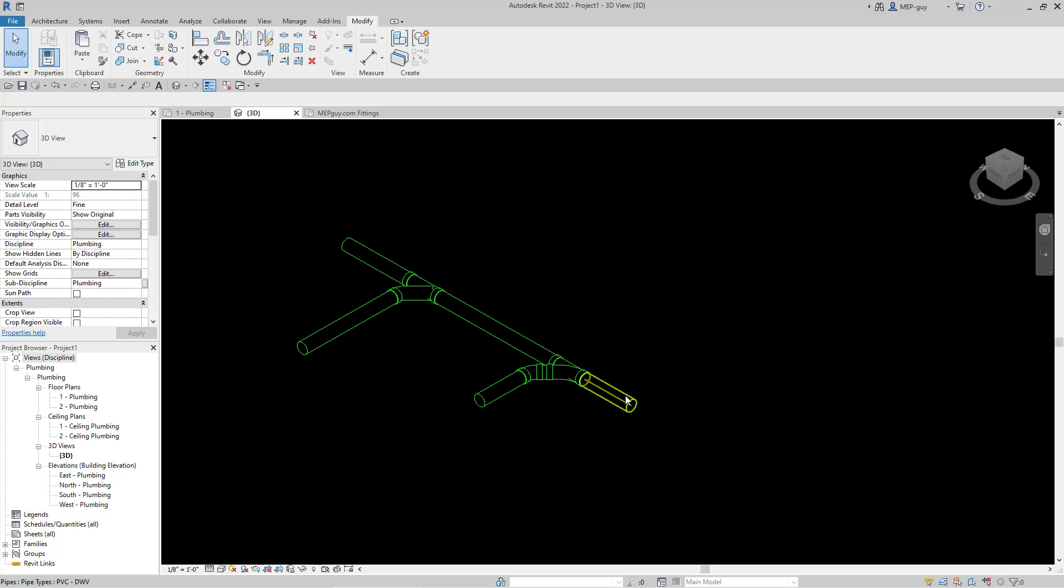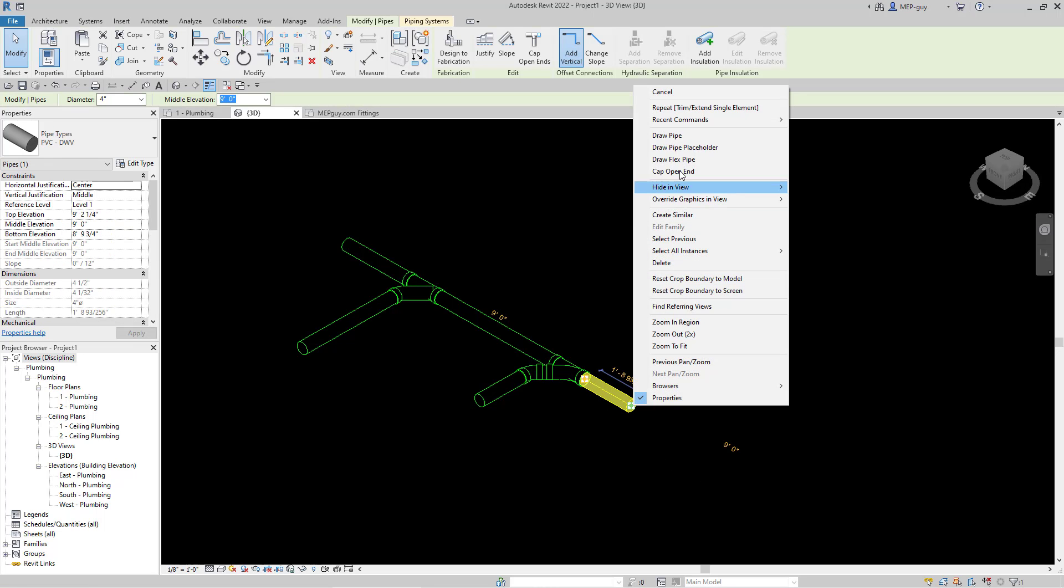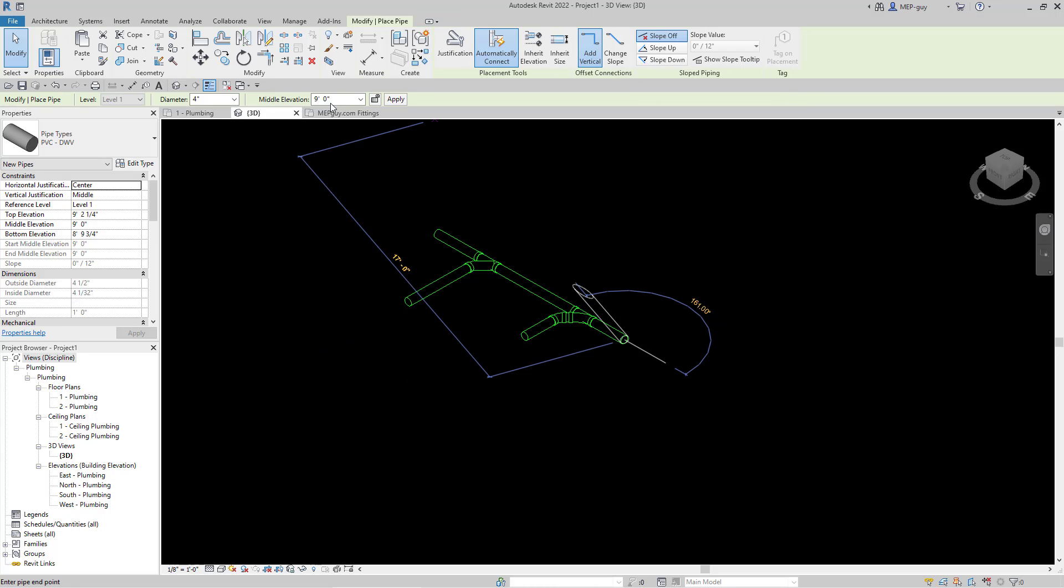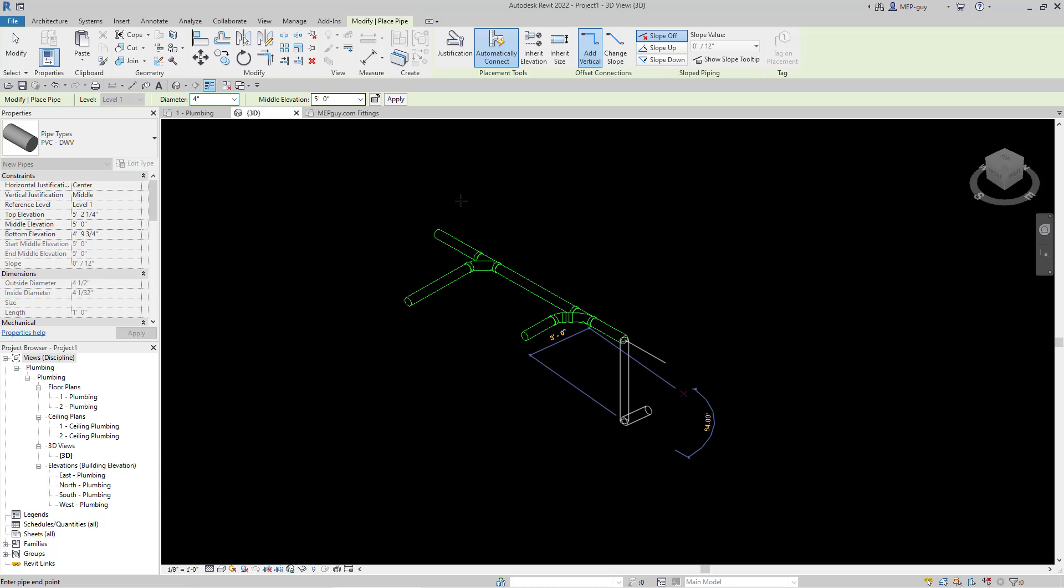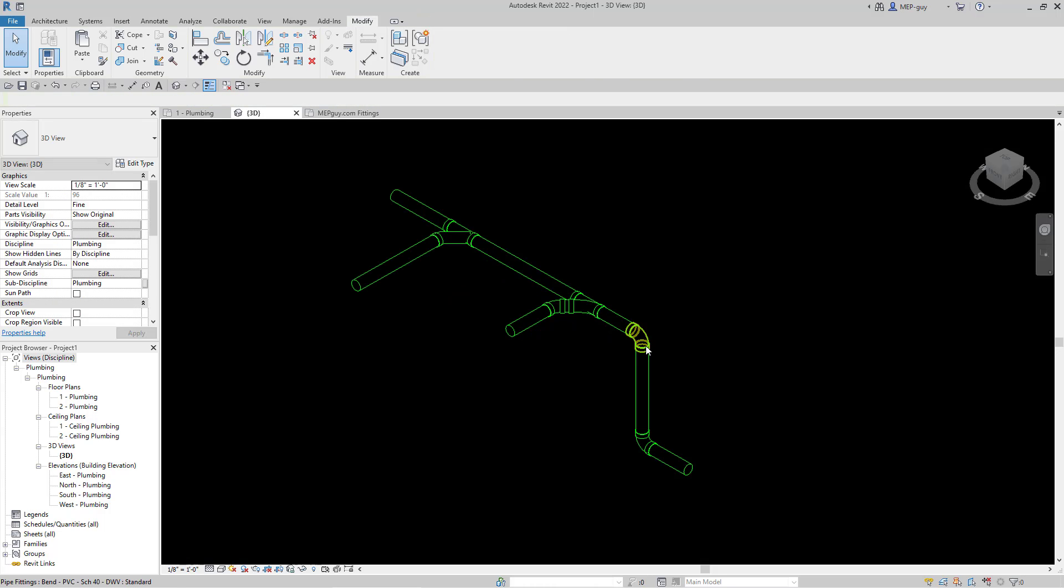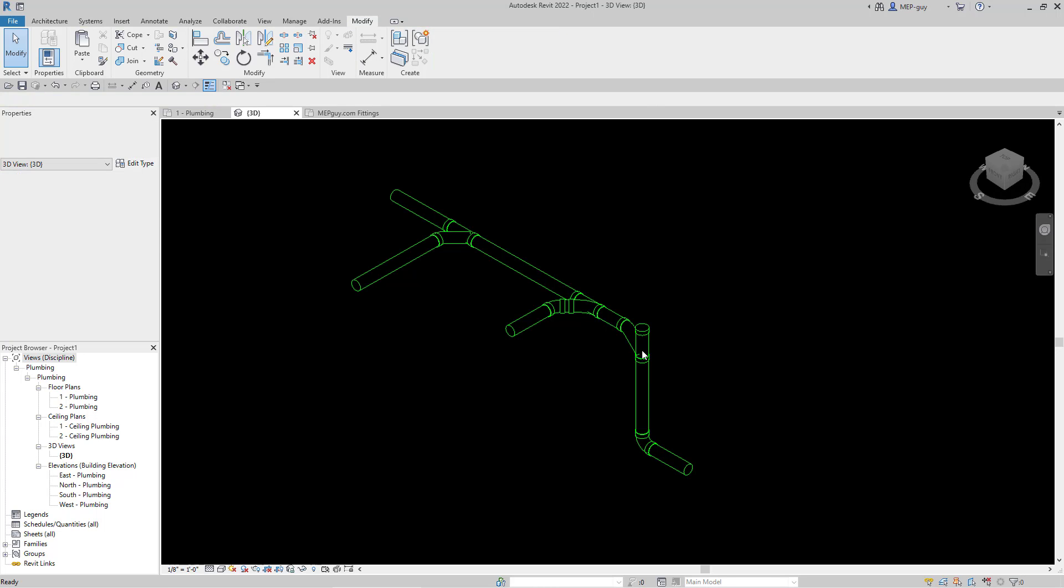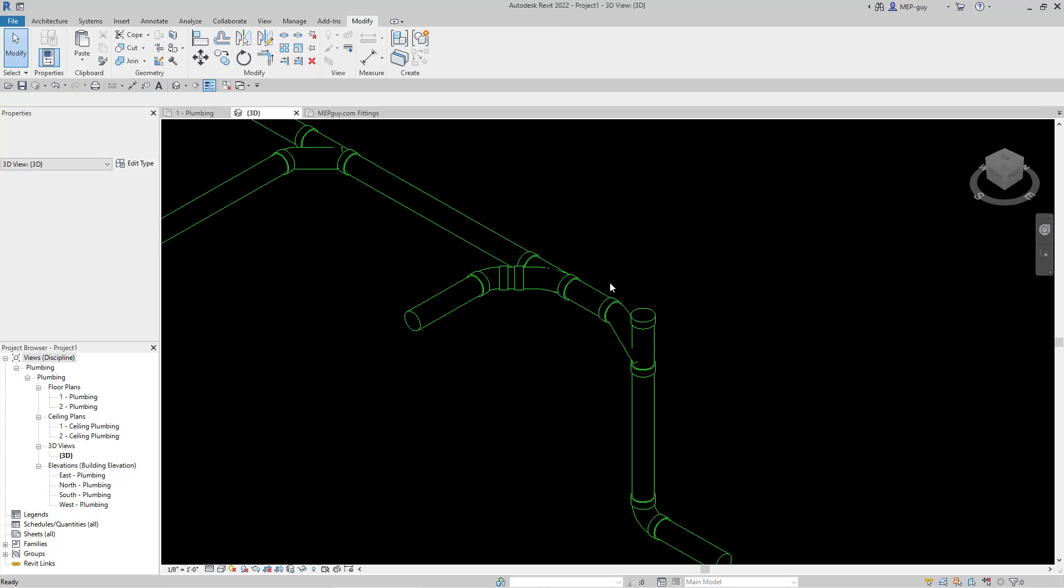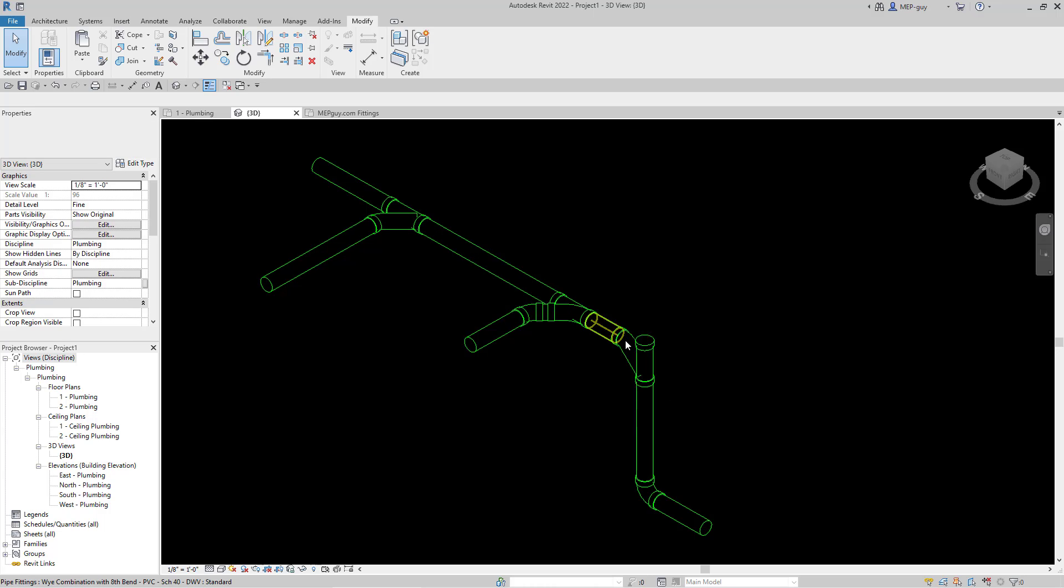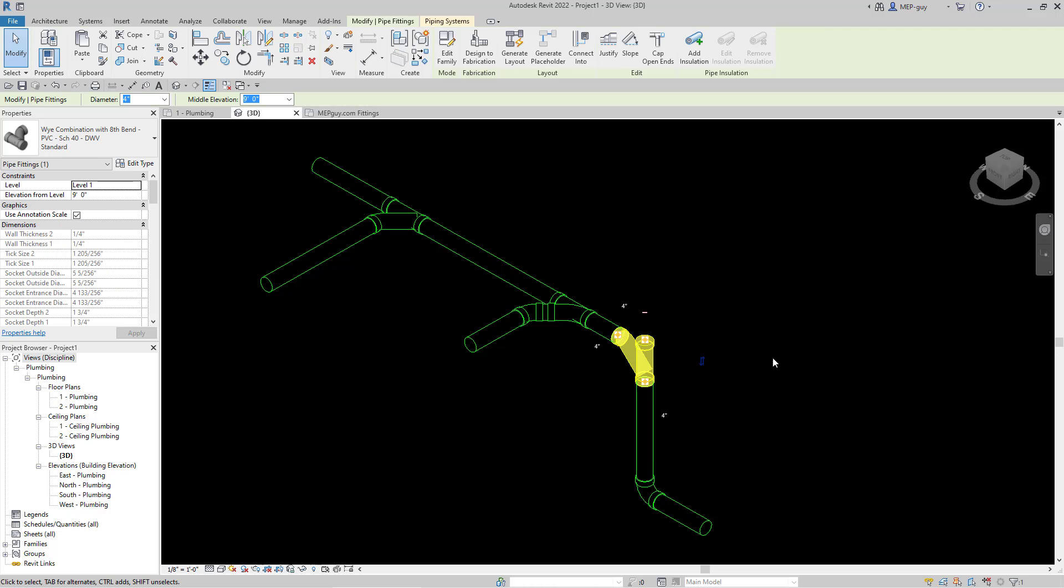Now we can use that T fitting when we are going from horizontal, and I'm going to draw a pipe, and we're going to drop this down to 5 feet. And I'm just going to hold shift, and we're going to draw it out this way. Now if I want to make a T here, I can just select the elbow and hit the plus button. And that will create that T that we set up. Now this fitting is totally fine. It gives us a nice sweep like we talked about into our vertical piping. But this fitting is actually more expensive. So we might actually want to use our sanitary T in this case only.